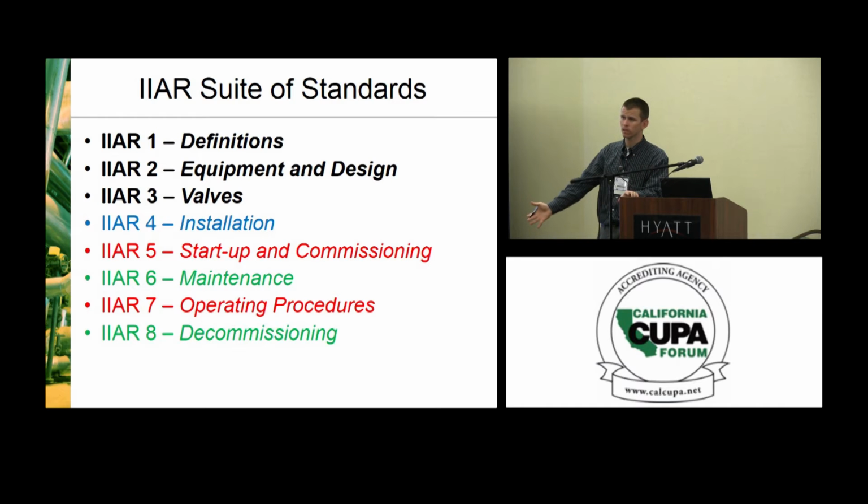That being said, ammonia pressure vessels are not permitted in the same way that, let's say, air compressors and boilers are. They're not permitted in that fashion. But to be a certified pressure vessel manufacturer, you have to go through rigorous protocols to satisfy that. And what you're looking for as an inspector is the nameplate, and you're looking for the little clover, the ASME clover punched on it. Usually it has a U inside that clover, which tells you it's an unfired pressure vessel. Unfired means it's not a boiler, it's not got flames under it in any way.